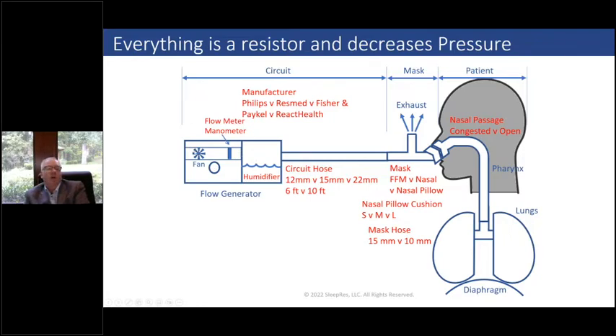Once that pressure comes off here, it's going to hit a flow meter, hanging down to measure the flow. It's going to cause resistance, therefore you've got a pressure drop. It's going to cross the humidifier, another pressure drop, usually small, and then it's going to go down the hose.